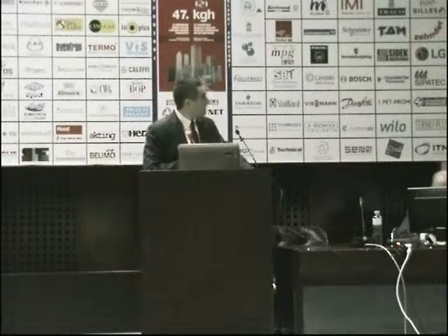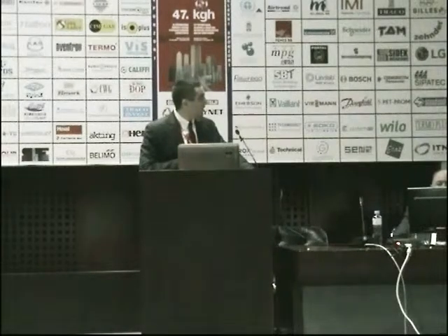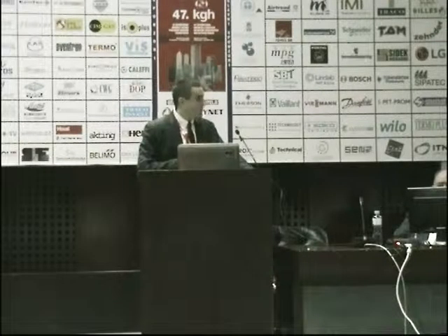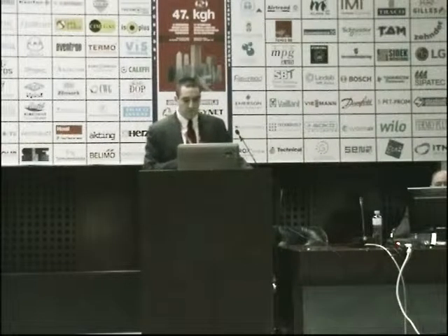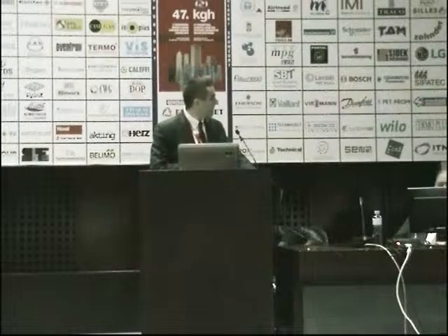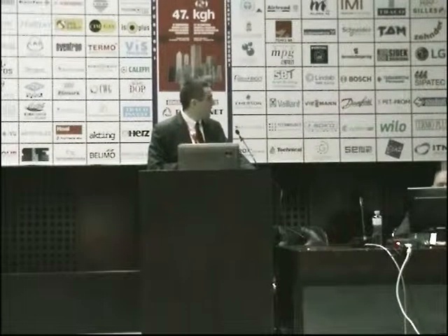The cold water was induced in the heat exchangers from the secondary circuit with cold water, and water was cooled in the primary evaporator. The primary refrigeration machine was a chiller with zeotropic blend R407C. Volumetric flow rate of water was measured at a balancing regulating valve, and also a 3-step circulating pump was used.